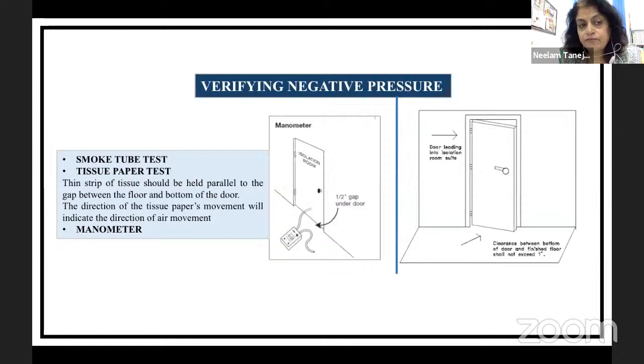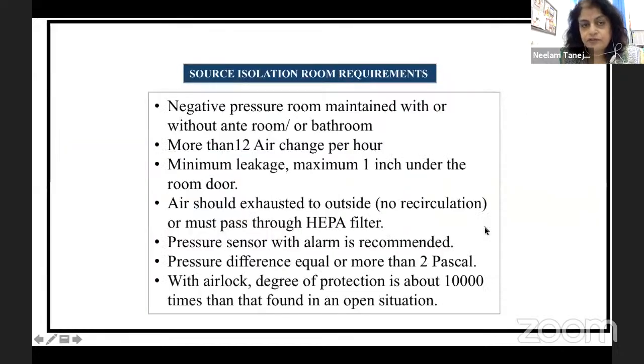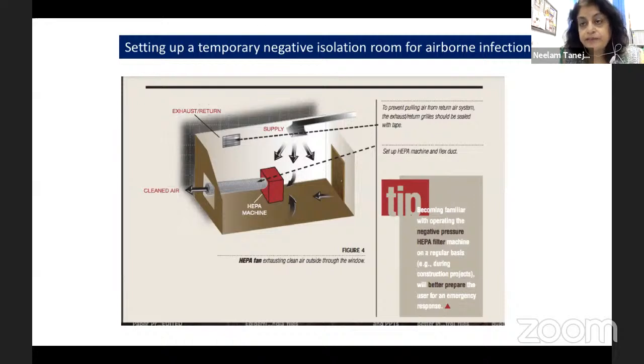You have to verify the negative pressure by doing a smoke tube test, or you could do a tissue paper test. This strip of tissue paper should be held parallel to the gap between the door and the floor at the bottom, and the direction of the tissue paper's movement will indicate the direction of the air movement. Most important is that it should prevent the leaking of the air, and this gap should be less than 1 inch. There should be more than 12 air exchanges per hour. A pressure sensor with alarm is recommended, and the pressure difference should be equal to or more than 2 pascals. 2.5 pascal is good enough. With an airlock, the degree of protection is about 10,000 times more, but they are very expensive and also may be difficult to maintain, especially in our settings.